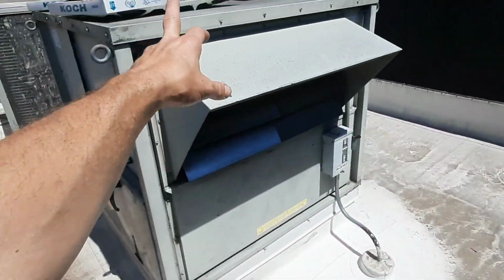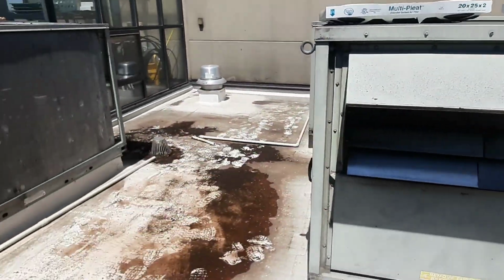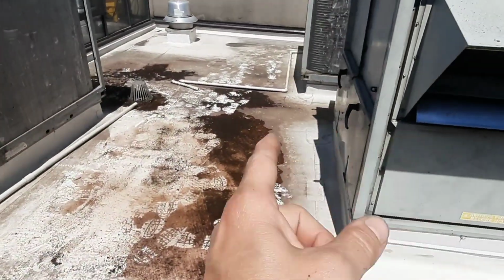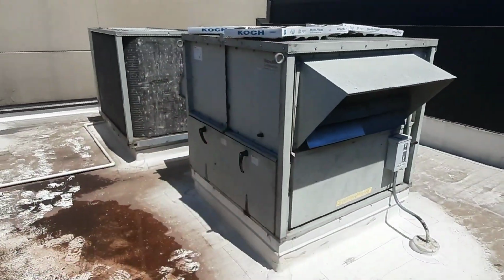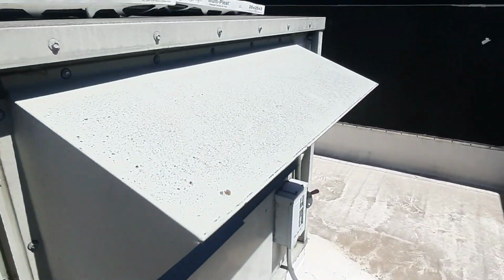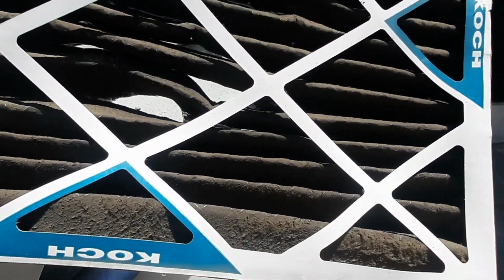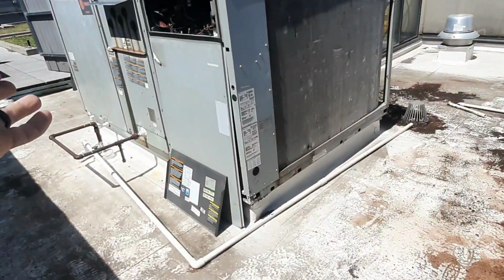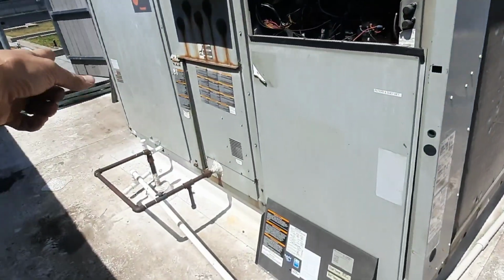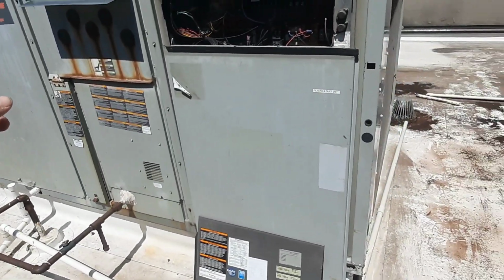So the only thing I really changed was I pulled these filters out, which if we're not air changing here, these were all designed to do with the ERV. So that really could have been affecting us. Although some of my filters don't have much of anything left, they obviously need to go. Everything needs to go. They need new belts, they need the coils cleaned, they need the filters changed on the rooftops, but the filters on the rooftops aren't affecting me too terribly bad right now.